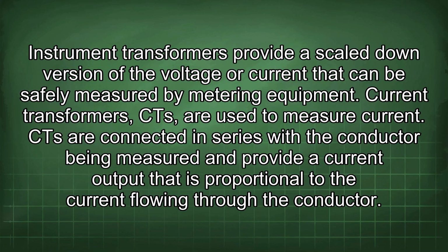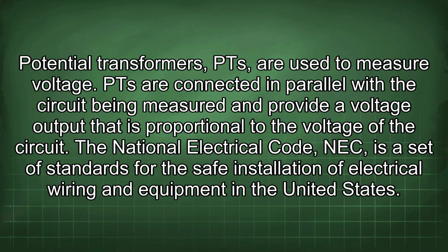Current transformers (CTs) are used to measure current. CTs are connected in series with the conductor being measured and provide a current output that is proportional to the current flowing through the conductor. Potential transformers (PTs) are used to measure voltage.